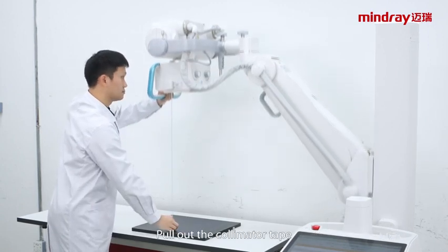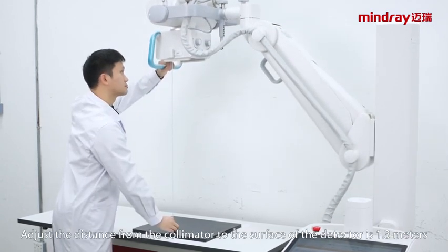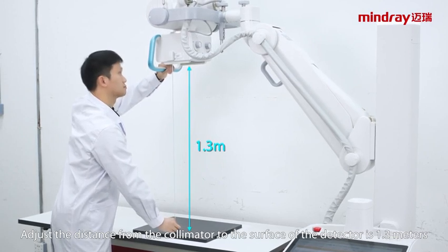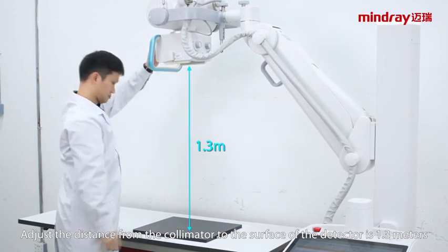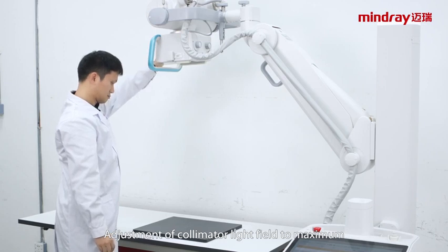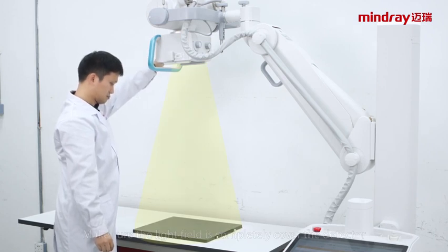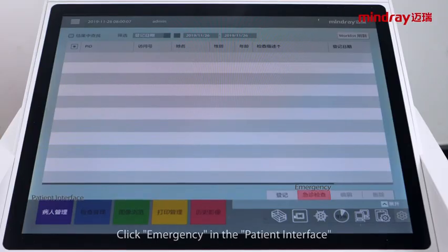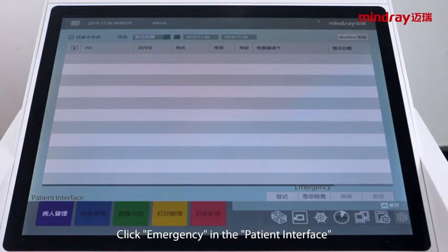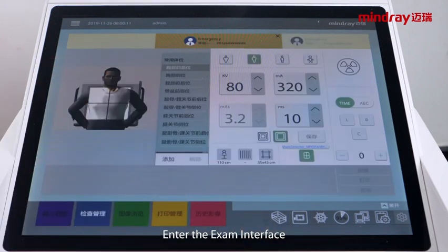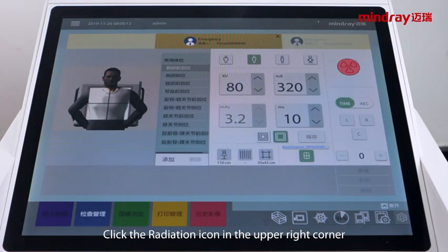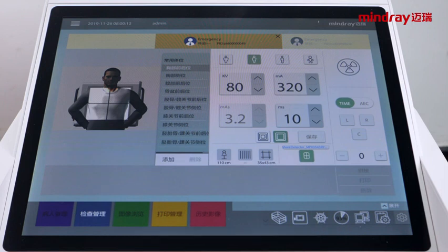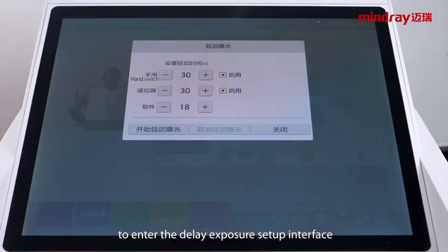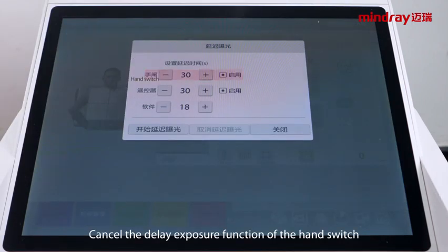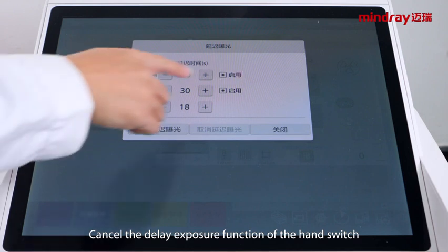Pull out the collimator tape. Adjust the distance from the collimator to the surface of the detector to 1.3 meters. Adjust the collimator light field to maximum. Make sure the light field completely covers the detector. Click Emergency in the patient interface. Enter the exam interface. Click the radiation icon in the upper right corner to enter the delayed exposure setup interface. Cancel the delayed exposure function of the hand switch.